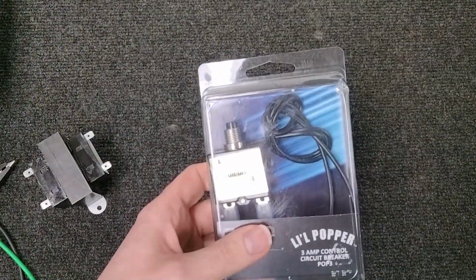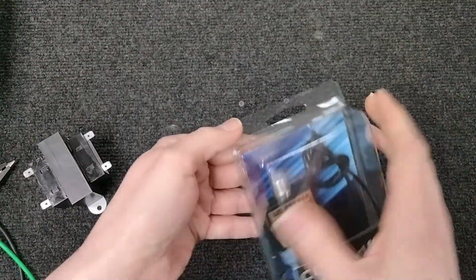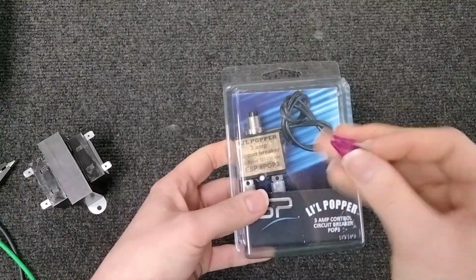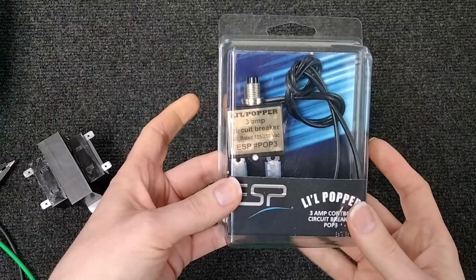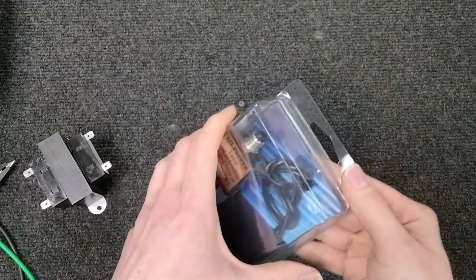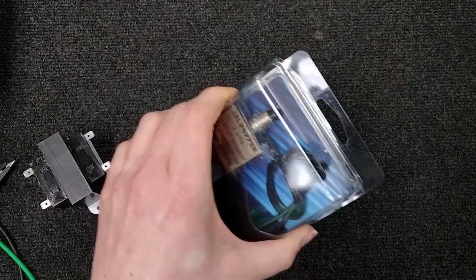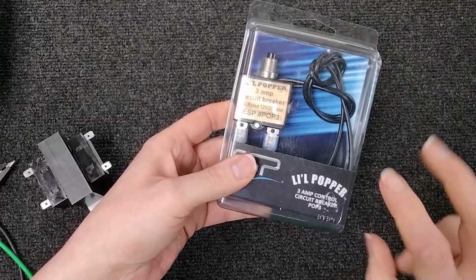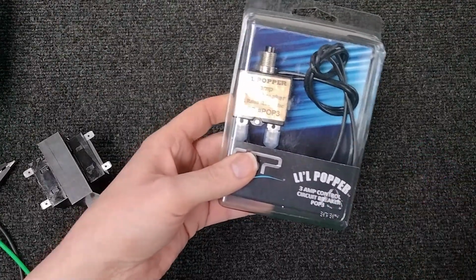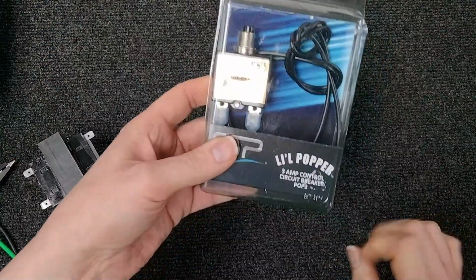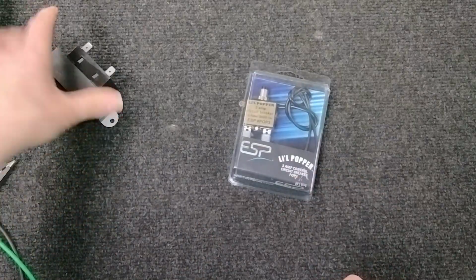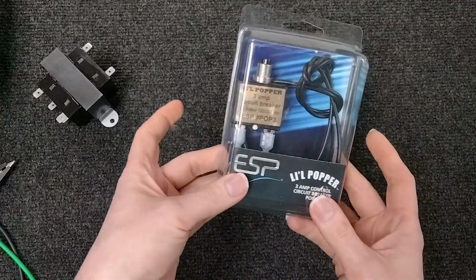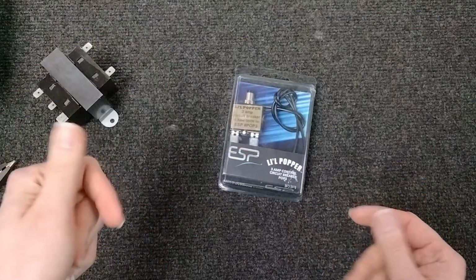Just as a side note, technicians, if you do find a popped fuse or a low voltage short, and this can go for homeowners too, honestly, don't buy something if it's just a matter of replacing a few fuses. But these are extremely helpful to have when testing. And you do not leave this in a unit. This is not a permanent fuse. It's a resettable fuse. So if this pops, it's just a matter of pushing a button in to reset it, and then from there you can locate where that short is coming from if you replace everything and you're still popping fuses. Again, we'll get into shorts and what you need to do to look for them, but for now, just know this is a good thing to have when diagnosing why the unit might not be coming on.